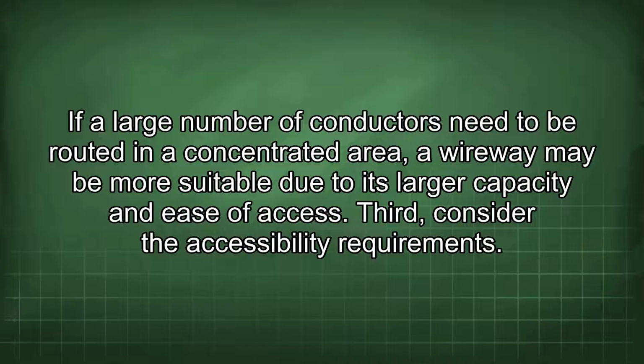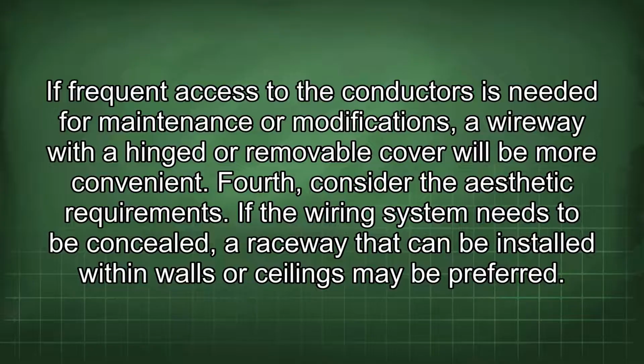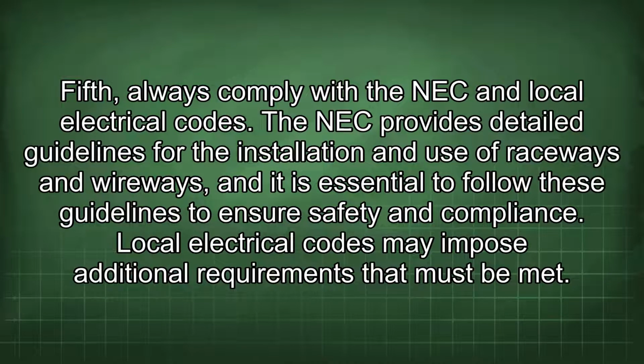Third, consider the accessibility requirements. If frequent access to the conductors is needed for maintenance or modifications, a wireway with a hinged or removable cover will be more convenient. Fourth, consider the aesthetic requirements. If the wiring system needs to be concealed, a raceway that can be installed within walls or ceilings may be preferred. Fifth, always comply with the NEC and local electrical codes.